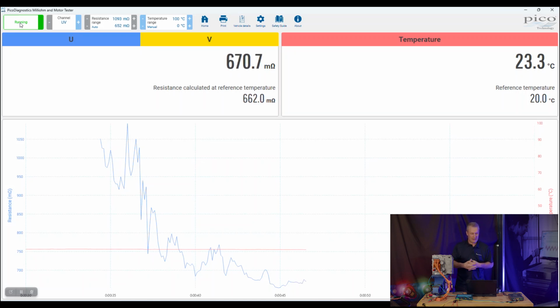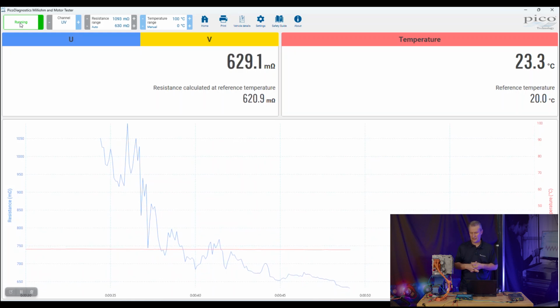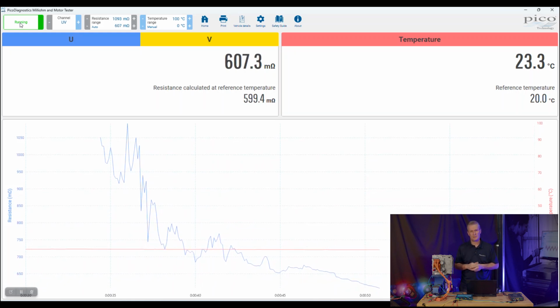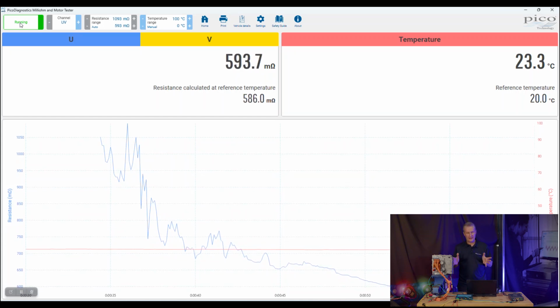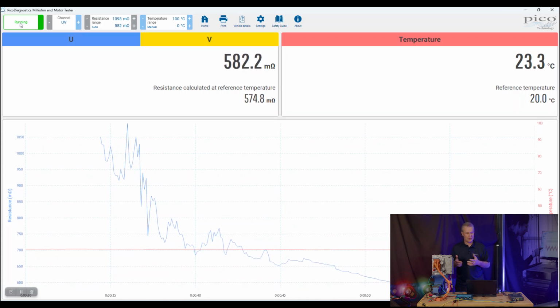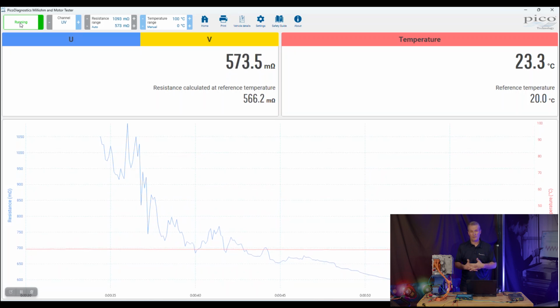What originally we may have thought was a good contactor, in fact at 170, 180 milliohm recorded with PicoScope and the BNC Plus resistance probe. By comparison to what we've got here, they're both a fail, but this is measuring now to a higher level. So if it was that you had both contactors working, but one of them had a resistance of 500 milliohm, that is a fail.